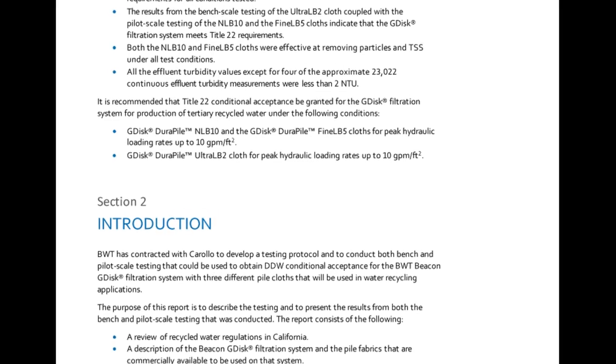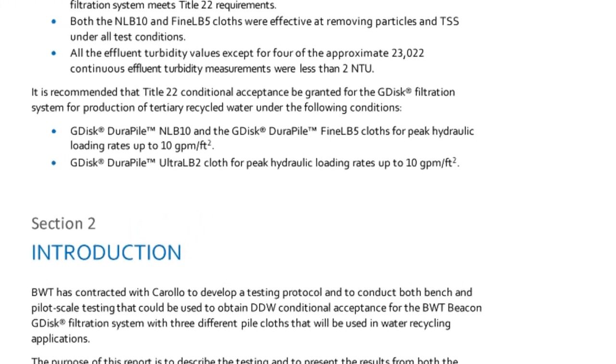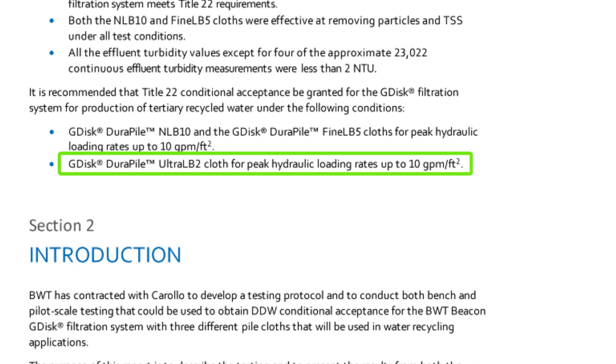Carollo has recommended to DDW that Title 22 conditional acceptance be granted for Beacon G-disc filtration systems under the following conditions: G-disc Durapile NLB10 and G-disc Durapile Fine LB5 cloths for peak hydraulic loading rates up to 10 GPM per square foot, and G-disc Durapile Ultra-LB2 cloth for peak hydraulic loading rates also up to 10 GPM per square foot.